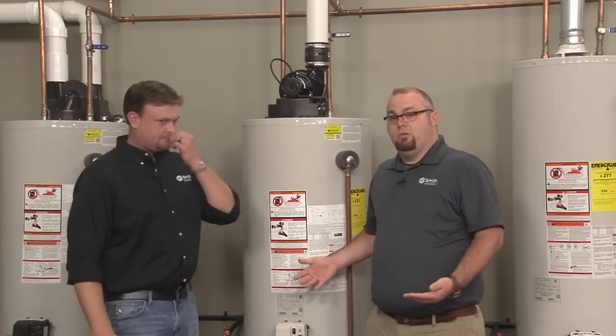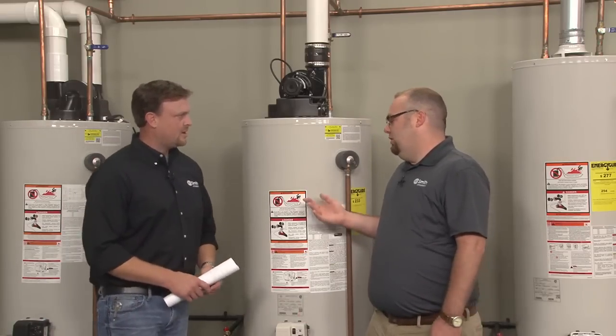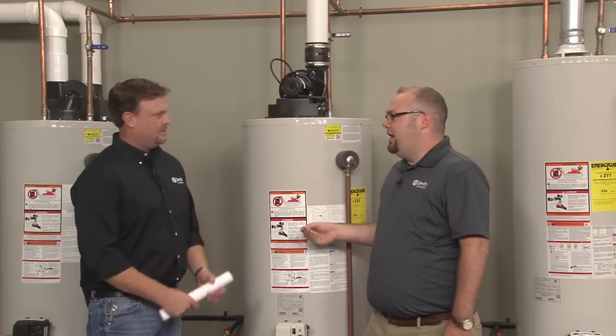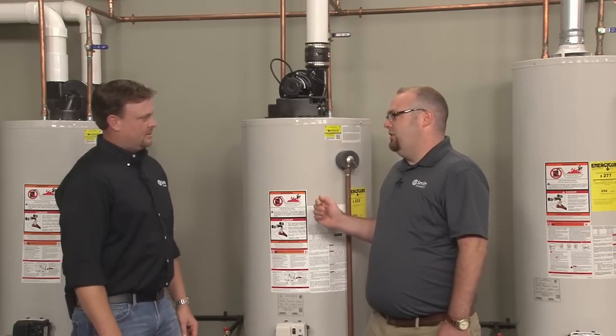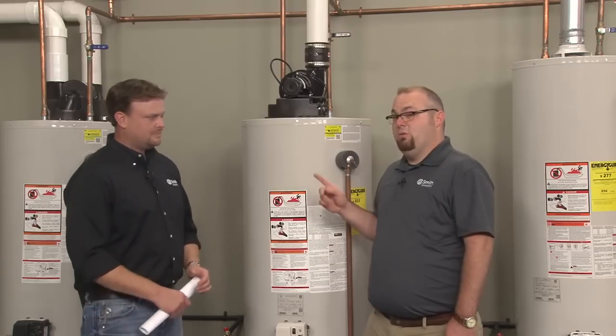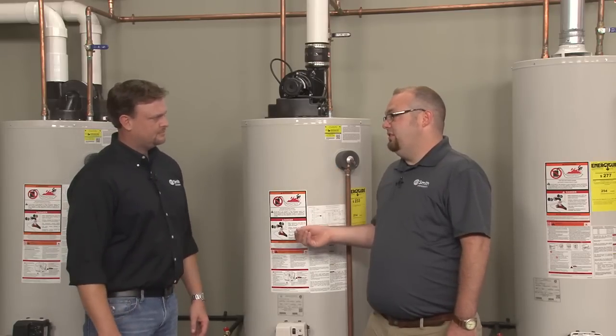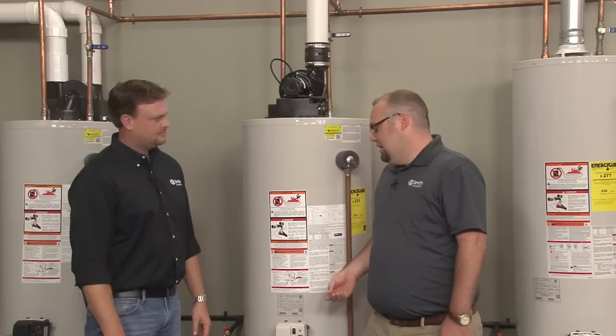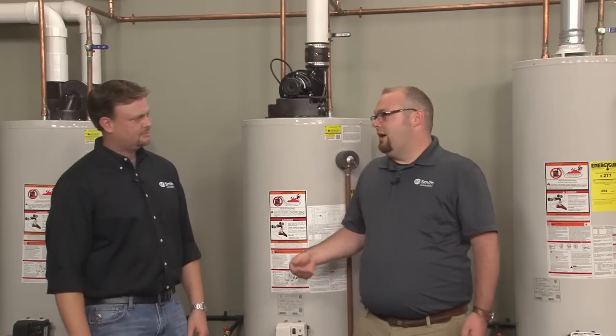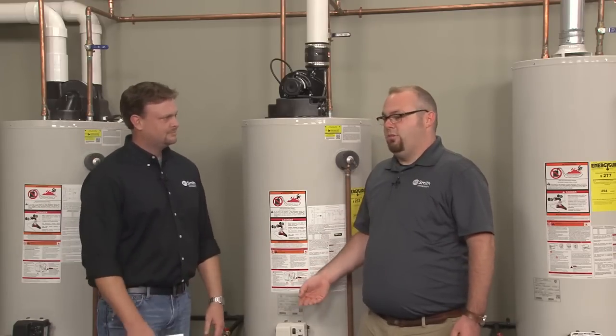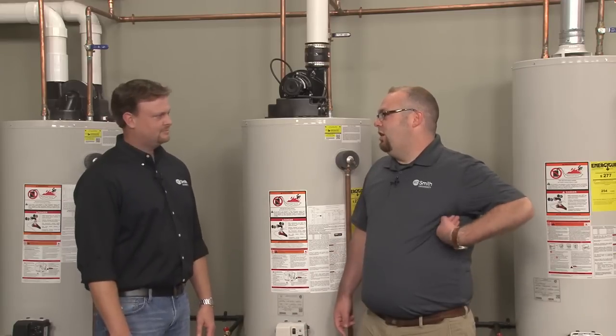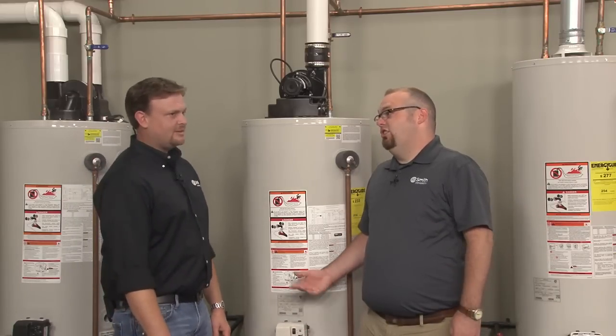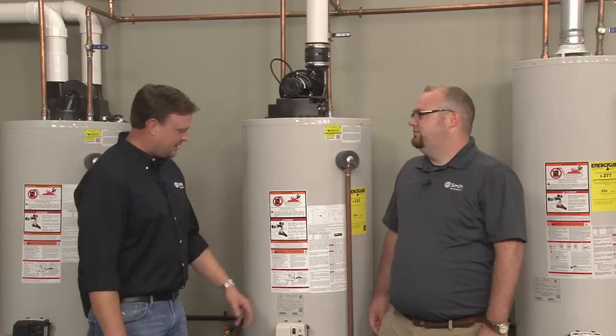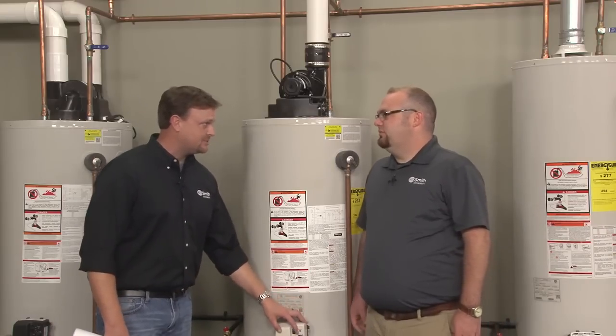But that's a good way we cut down on nuisance trips on the newer heaters: if the fumes go away quickly, it automatically resets. Now, within 1 minute, did you say? It has to be within 1 minute of detecting the flammable vapors. Of course, if the flammable vapors stick around a lot longer because you're cleaning your motorcycle chain right beside the water heater in a bucket of gasoline, you're going to lock the heater out. Yeah, I understand. Now, you said there is a reset procedure, so let's talk about that.